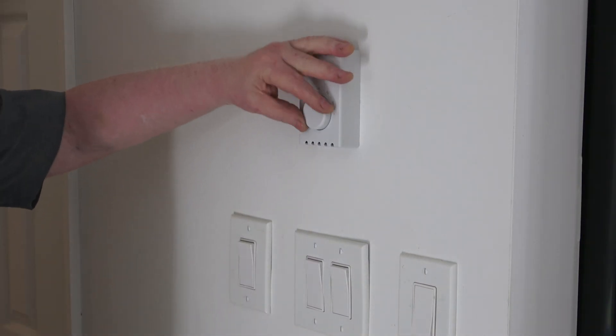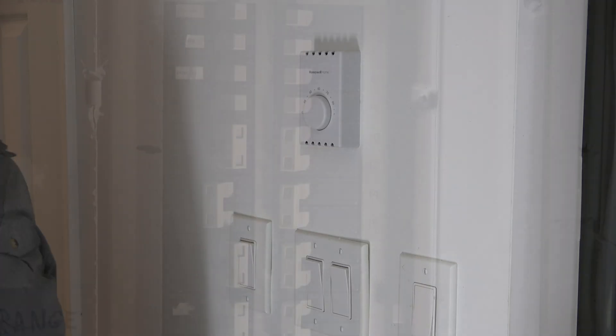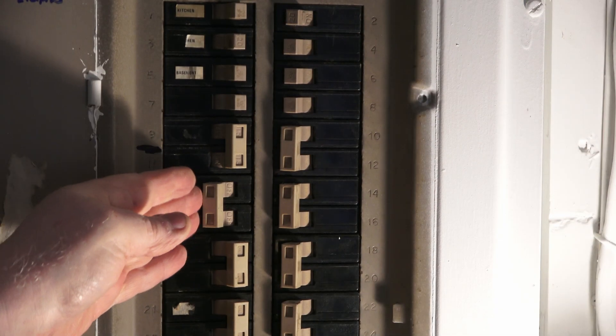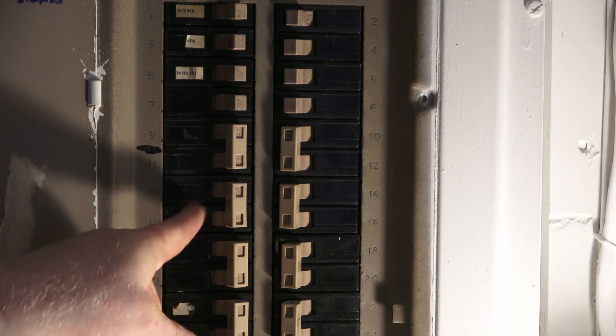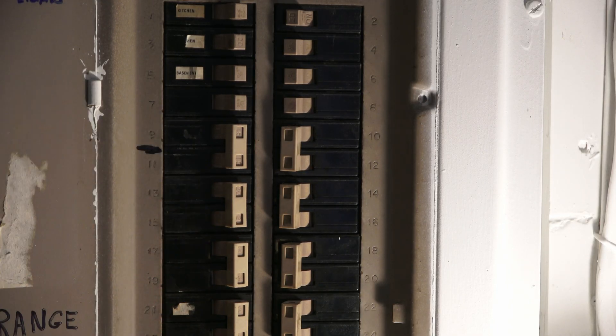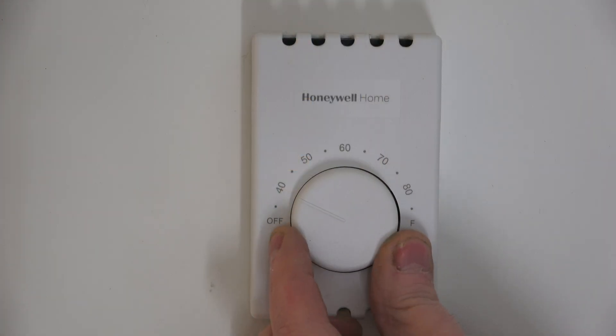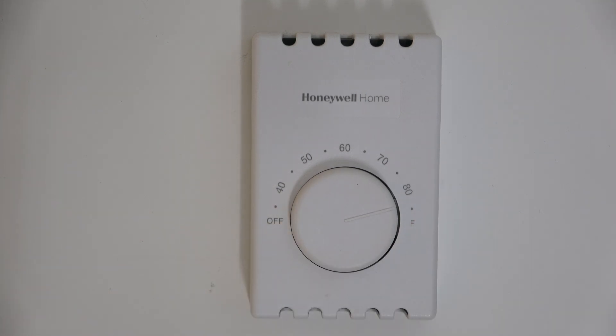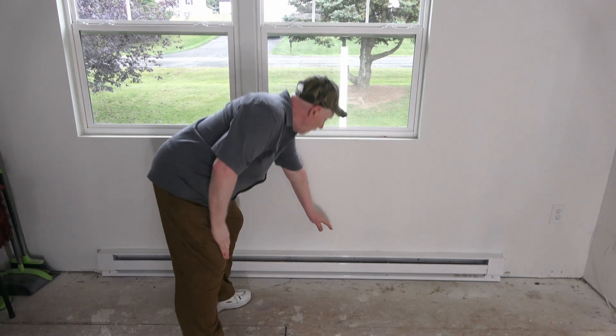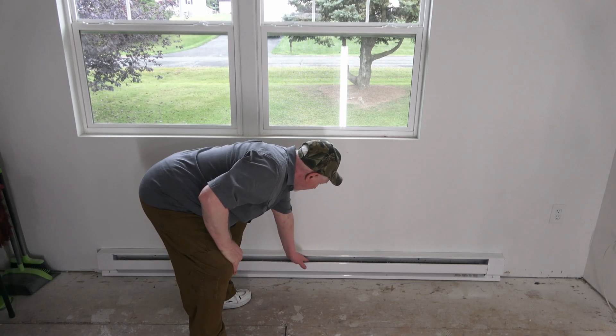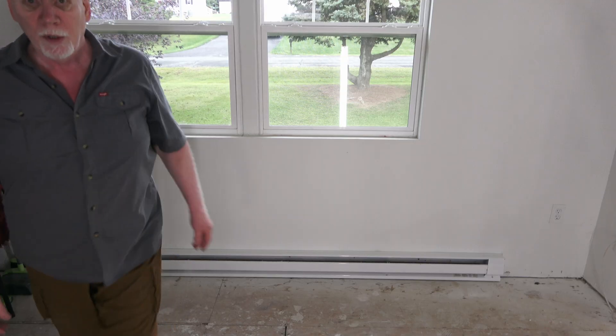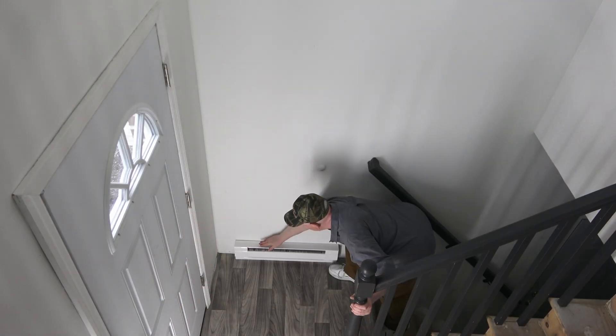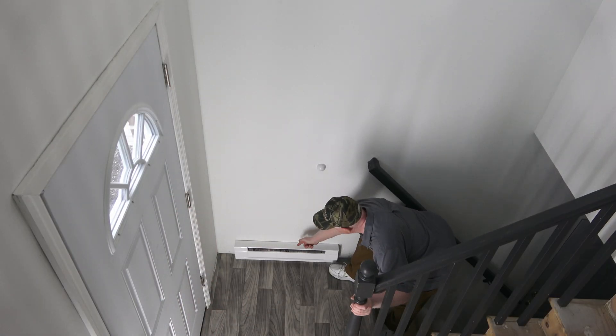Set the thermostat to off. Go turn the breaker on. Now that's a good sign. If you had something wired wrong, it would trip. However, we still got to turn on the thermostat to make sure it's good. Turn the thermostat all the way up to ensure the heat comes on. Yes, that's heating up quite nicely. I'm going to check the other one. Very nice. Success.